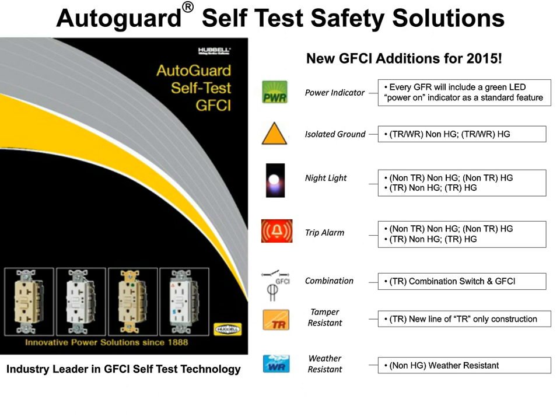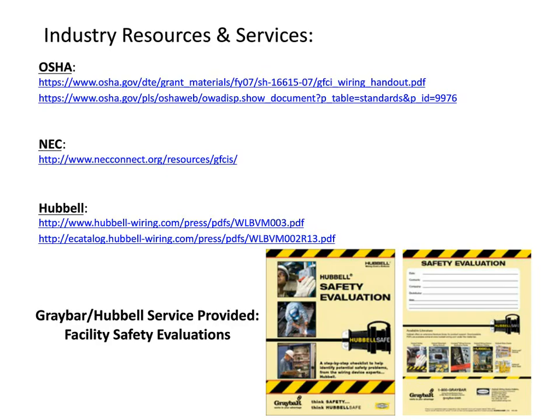You might have a ground fault on a soda machine, a refrigerator, or it's located in the basement or an area that's not frequently populated. So you want an audible alarm built into that ground fault to tell you if it trips. So there are multiple varieties of new ground fault products out on the marketplace, in addition to the tamper resistance that has been out on the market for about 5 or 6 years now. With this standard, you're going to see some new products from not only Hubbell, but from all the manufacturers, with regards to safety and the ability to monitor the circuits, et cetera.